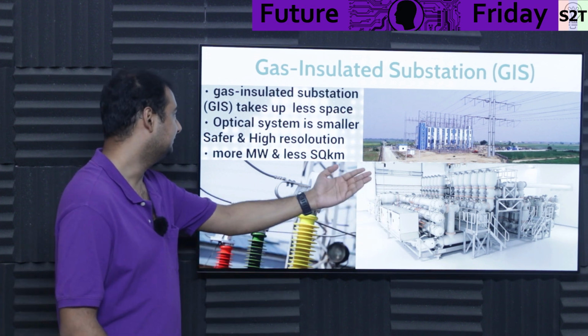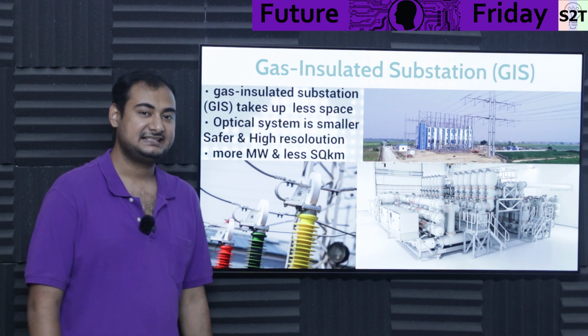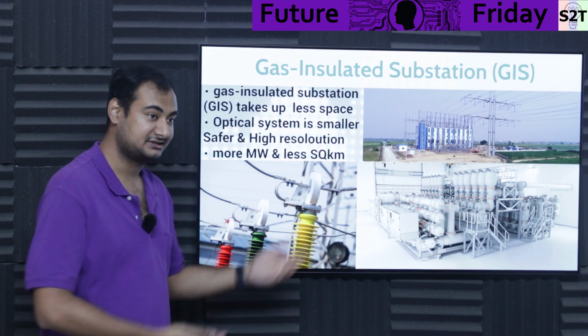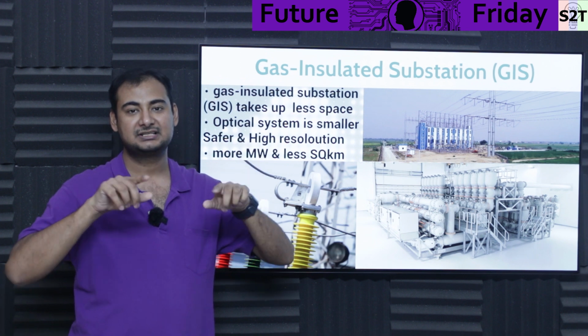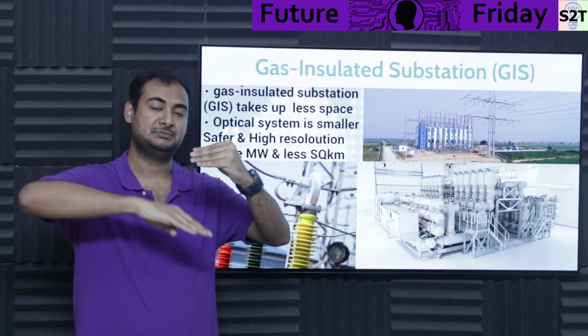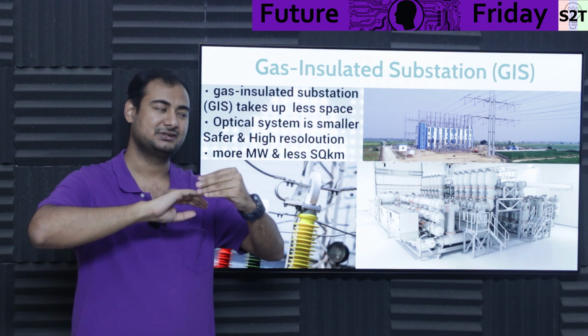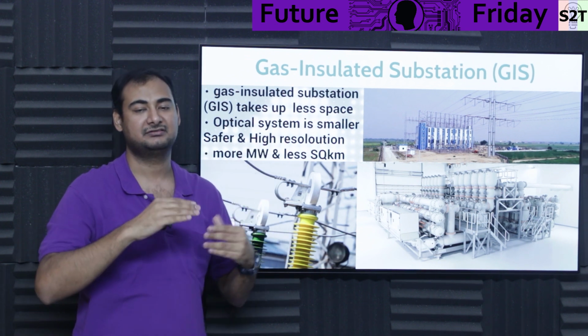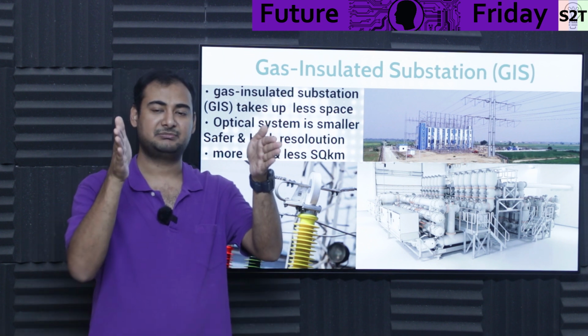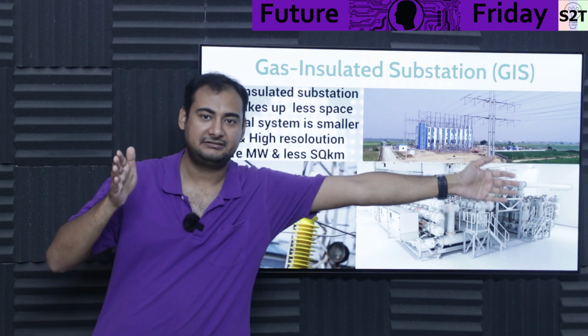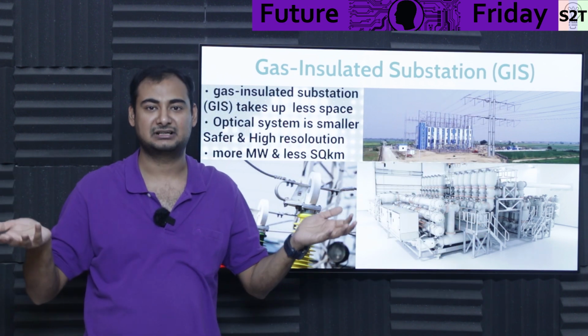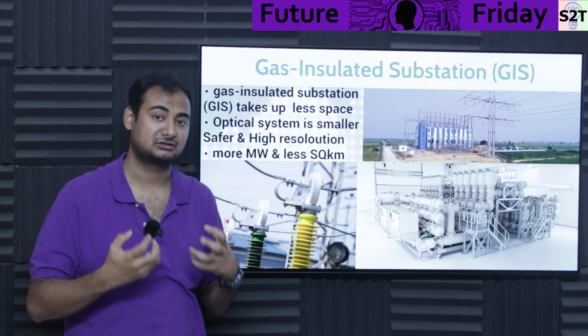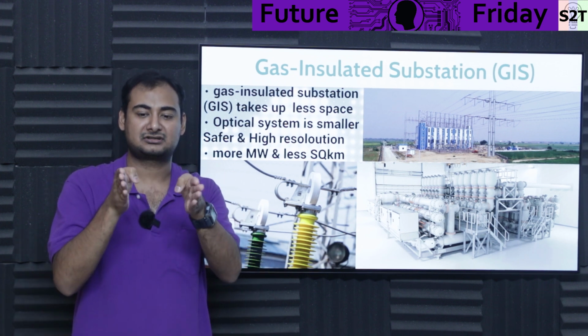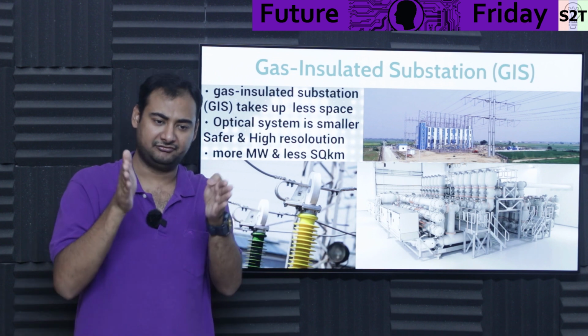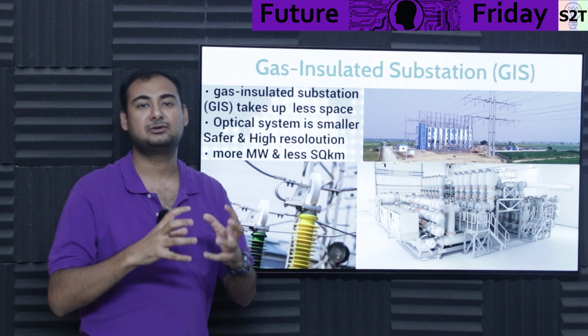Thankfully we have this: GIS, gas insulated switchyard. I'm not sure why it's called switchyard instead of substation, but the logic is this - substations are huge because each cable has an imaginary sphere or pipe around it, which is where electricity would jump if there's another conductor nearby. So at 100 kV you need a certain gap, at 33 or 11 kV a different gap - everything is about the gap. But with gas insulation, which has much stronger insulation properties, you can have two conductors carrying as high as 500 kV very close together, letting you compact everything.